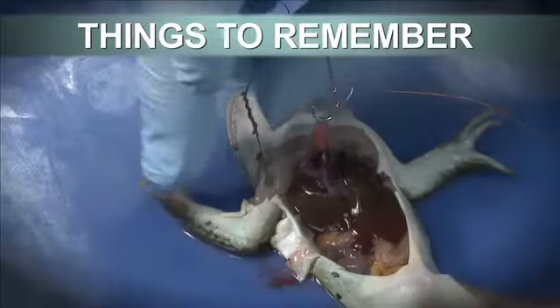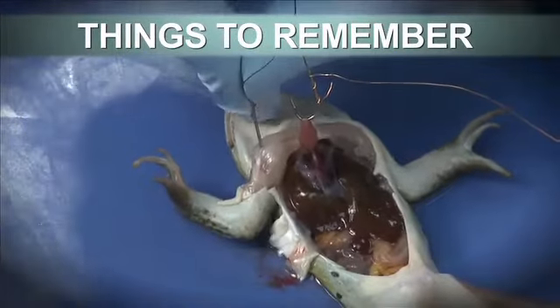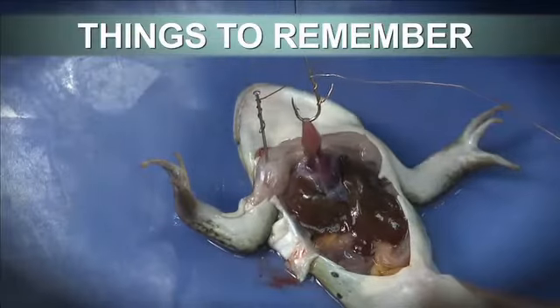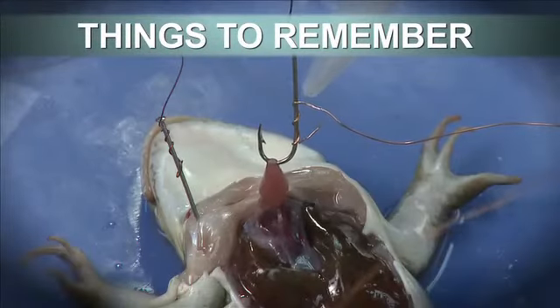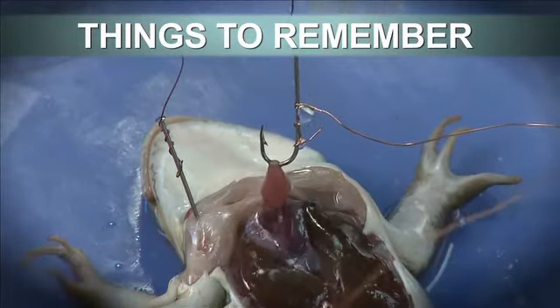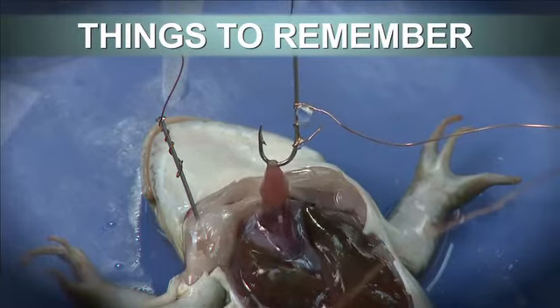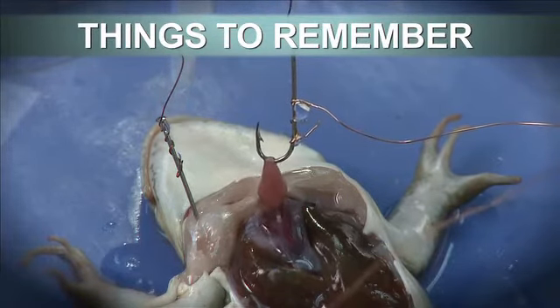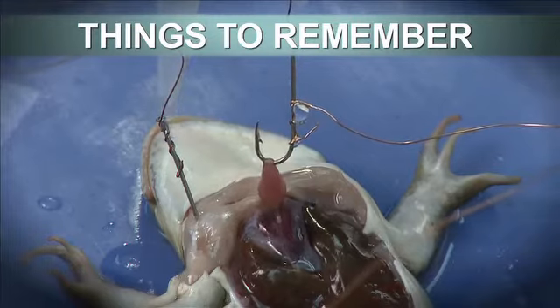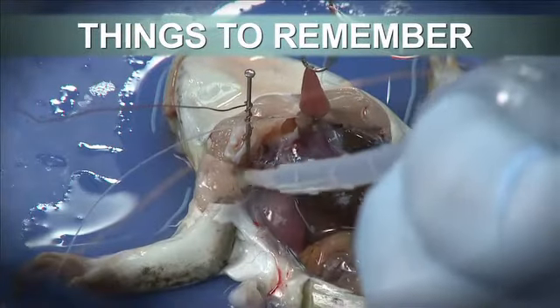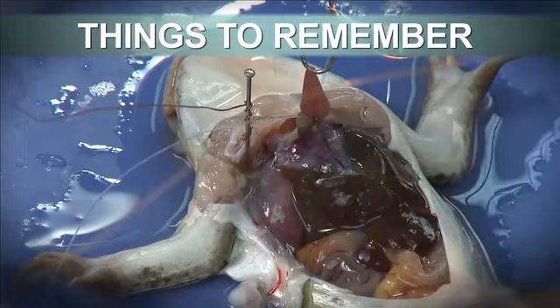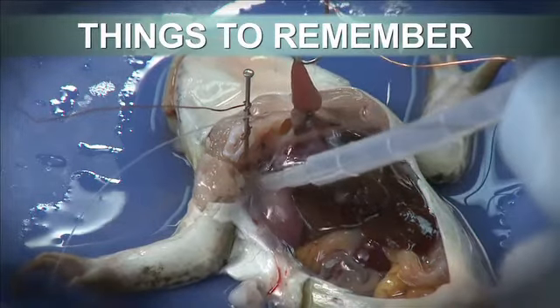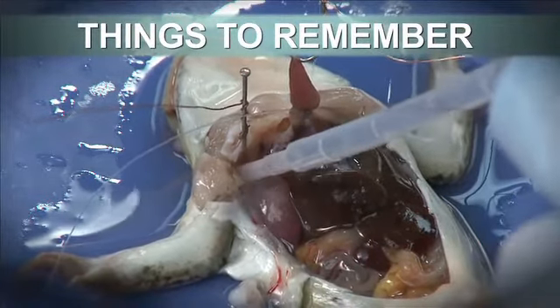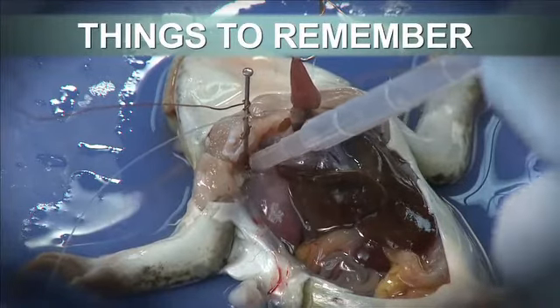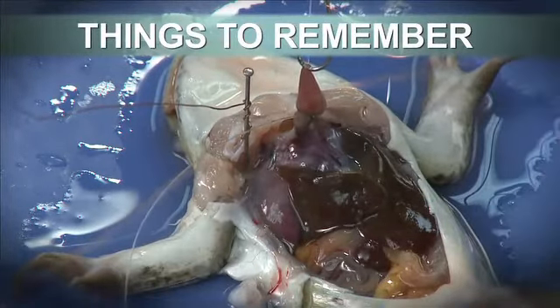Some important things to remember this week. In order to get a nice ECG signal, always maintain good connections between tissue and wires. If signals become noisy, you might want to apply a couple drops of Ringer's to improve the connection. If the mechanical signal looks good but the ECG signal does not, you might need to remove the Ringer solution, as the electrodes may be bathed in it. This is a typical problem for the positive recording electrode, since the shoulder region often holds extra fluid.